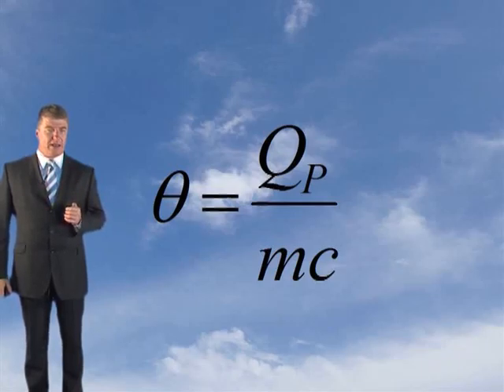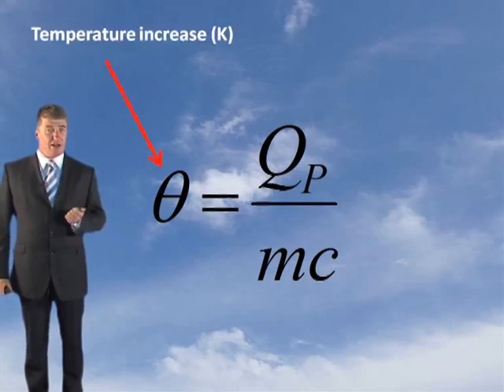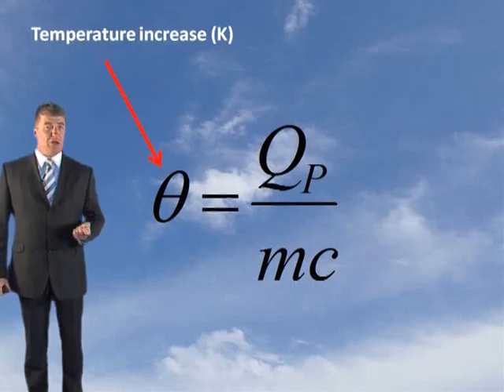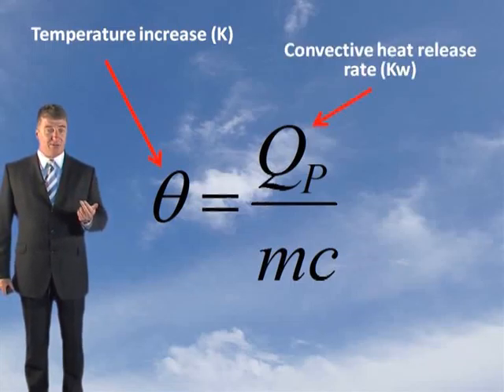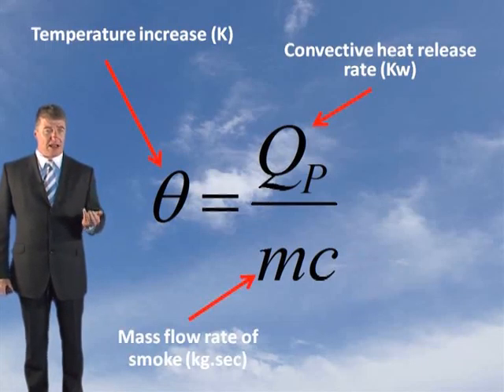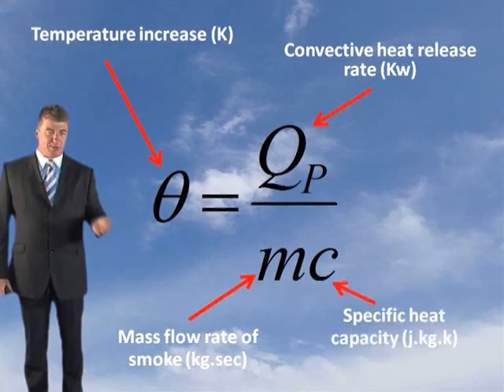Firstly, we need to determine the temperature increase in the smoke. The formula to apply is: theta equals Qp divided by m times c, where theta is the temperature increase, Qp is the convective heat release rate, m is the mass flow rate of smoke, and c is the specific heat capacity of the smoke.